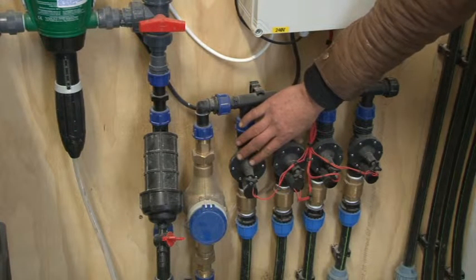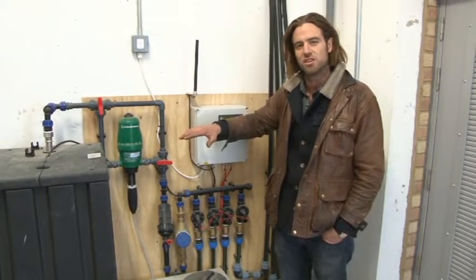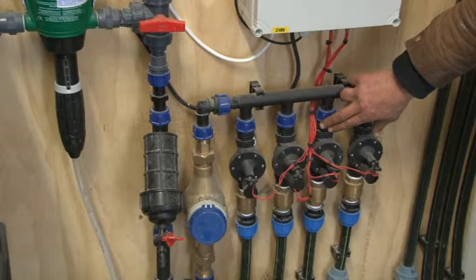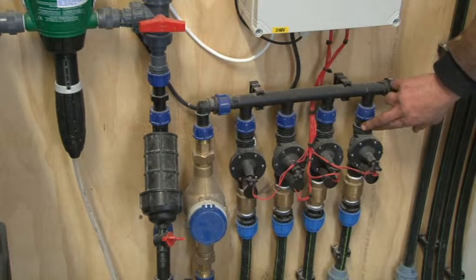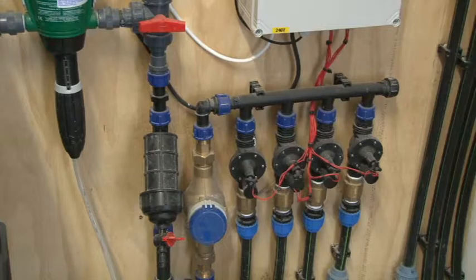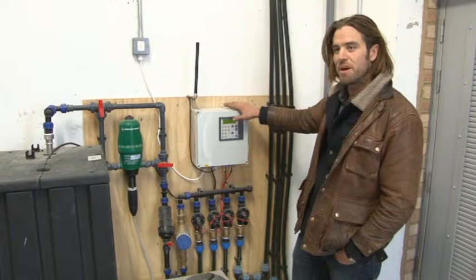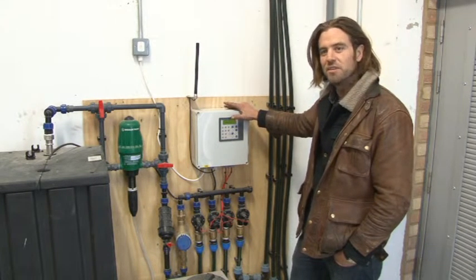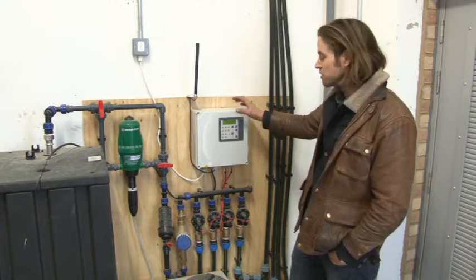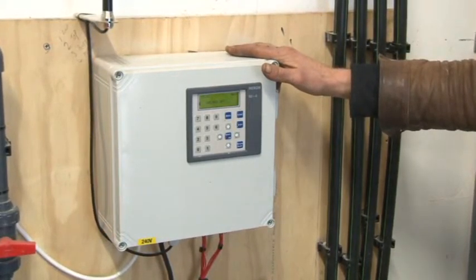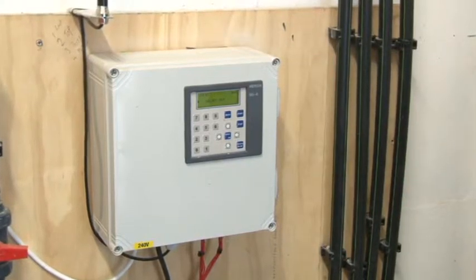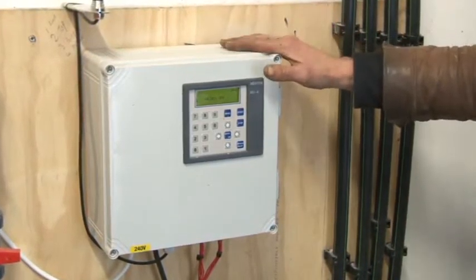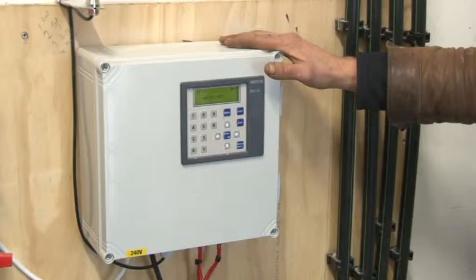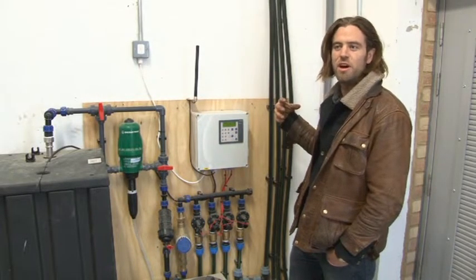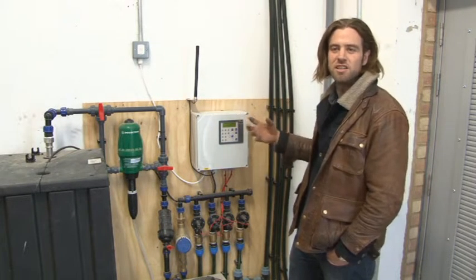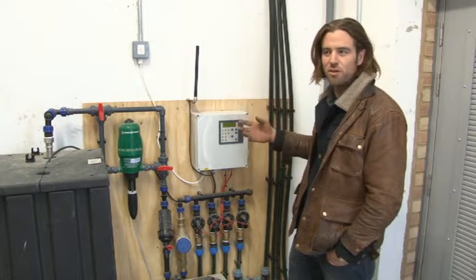There's 2 zones for the upper and lower section of the living wall, along with the screens and some beds up on the rooftop area. All the information is fed back up to the Heron controller here, which is monitored online. So this allows us to know whenever the wall's overwatered, underwatered, where there's a leak, there's a blockage. It also gives us the opportunity to change the irrigation cycles remotely away from site for changing of seasons, frost and so forth.